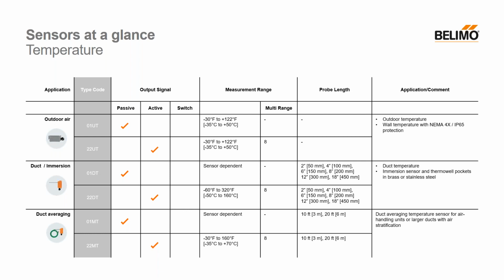And sometimes you can't assign that to a newer employee or a more green helper because the sensor can be easily damaged. With our duct averaging sensor, it's a cable style sensor. So it's either one continual PT or NI sensor or a sensor with NTC beads in it that does the averaging. So all you're doing is fishing a cable into that air handler. And again, our averaging sensor is going to come with harnesses and all the necessary mounting hardware that you would need to install a duct averaging sensor.